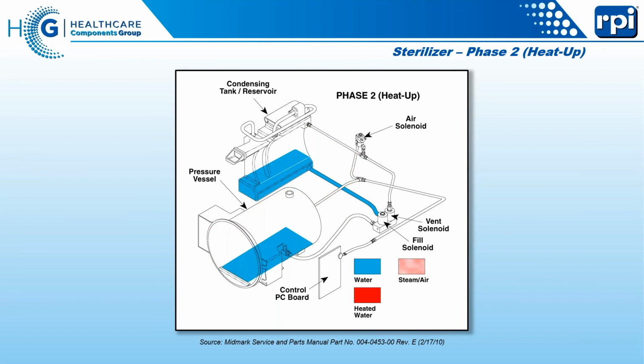The heater on a respiratory humidifier used to do the same thing because of the heating element inside the fluid warmer. Yeah, like isolettes or incubators, same problem. Anything that has a heating element to heat water doesn't like GFCIs: hydrocollators, anything that uses hot water. So replacing the heating element cures the GFCI problem? In some cases, yes. In most cases, it doesn't, because there's also leakage coming from the board as the board tends to age.